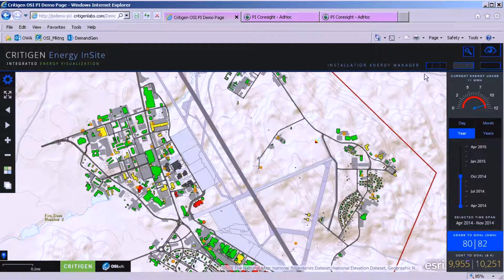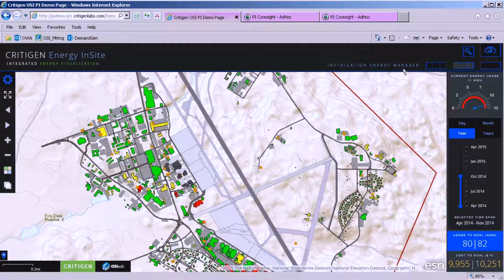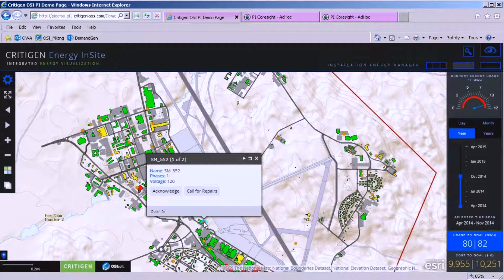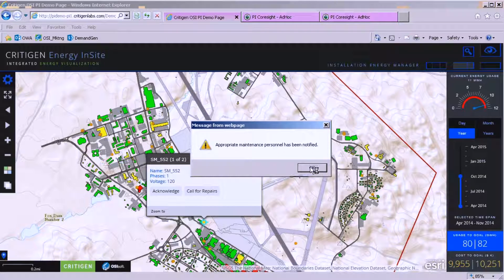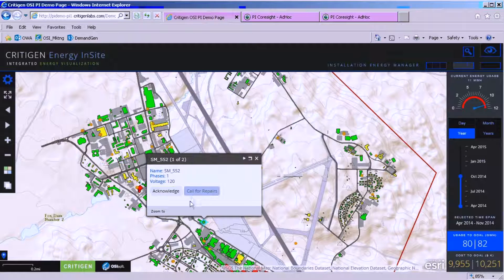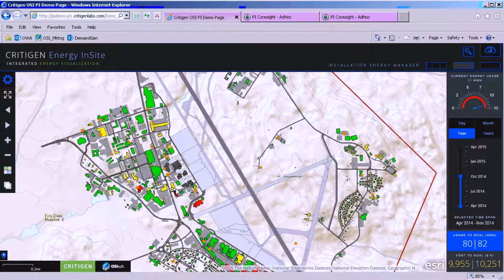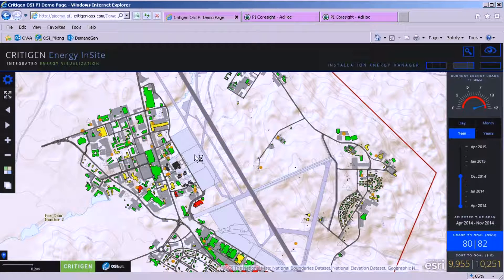As the installation energy manager, I pull up my display to see how my installation is doing and I have some blinking objects on my map. We've connected the GIS data to the PI database, so effectively the map is becoming your warning light. There's a meter here that's not reporting — meter 552. I can notify maintenance personnel and call for repairs, and once they've been notified, I can turn the alarm off. I also notice I have an outage — these gray buildings are not reporting, I'm not getting a PI feed from them.